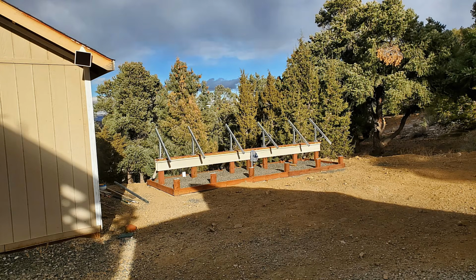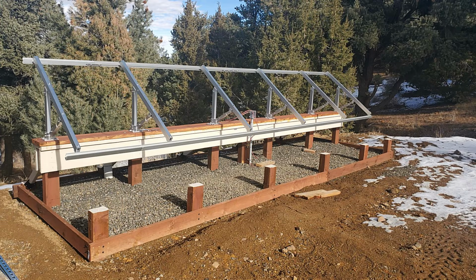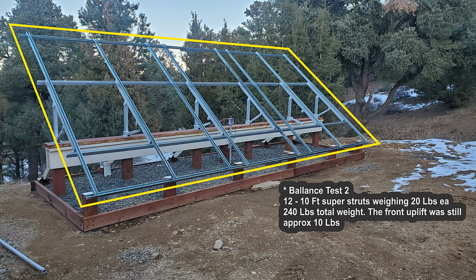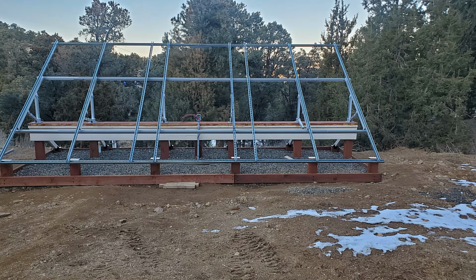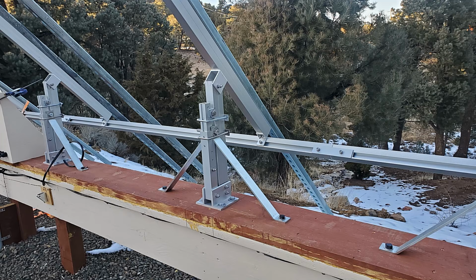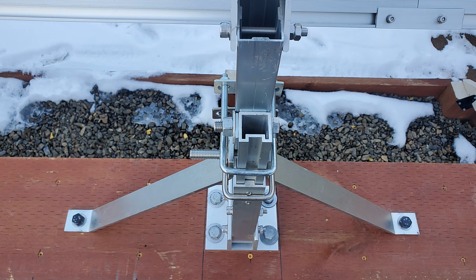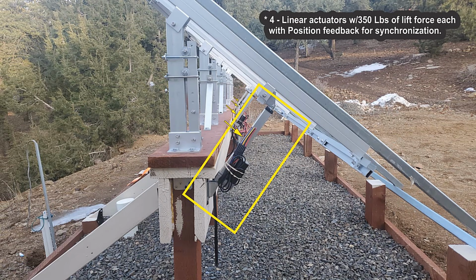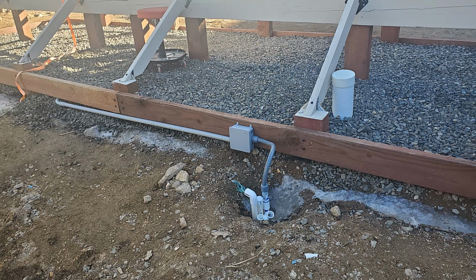What you're seeing here is the expanded version of the stock EG4 bright mount system. After mounting 12 10-foot superstruts to the EG4 base, I paused to test the balance point and verify that the added support would hold steady before proceeding. Once that was confirmed, I modified the vertical support arms as described earlier in the video and installed the linear actuators for precise tilt adjustment.